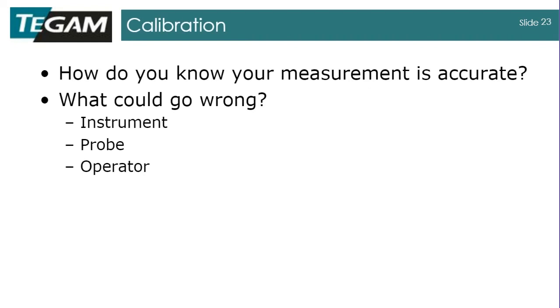And so how do you know your measurement is accurate? There are some things that could go wrong in this process. Obviously, your instrument could just be out of calibration. It is no longer adjusted correctly. It's reading wrong. And if that's the case, your number is going to be incorrect proportionally. Probes can become damaged. Some of the probes that get used are maybe subject to physical damage depending on the application and how hard they're used, and that needs to be checked periodically. And of course, the operator is also a source of error.